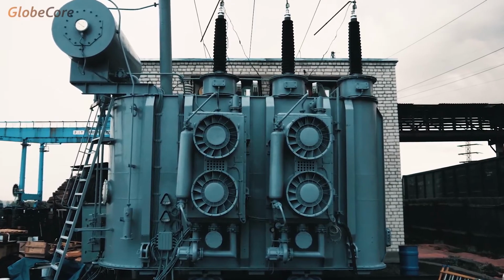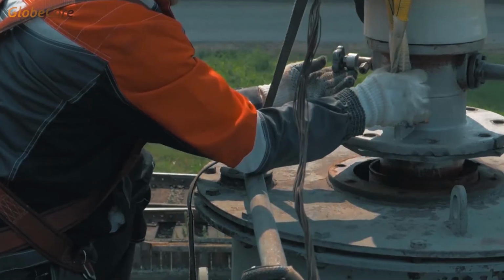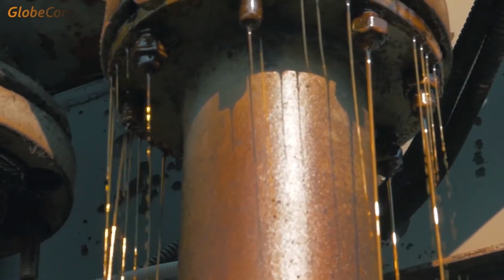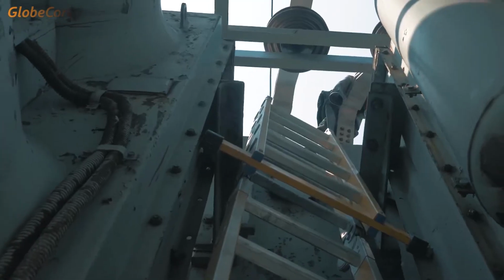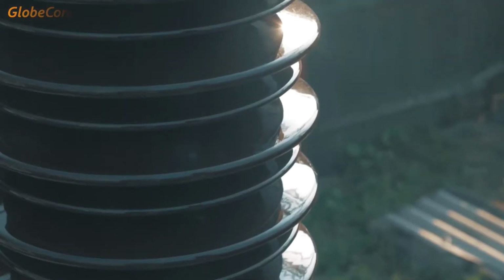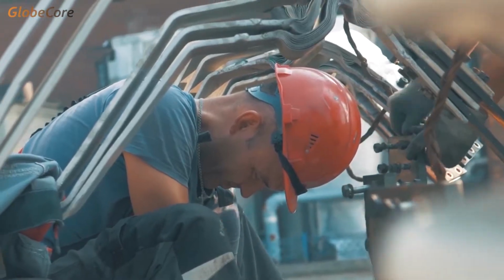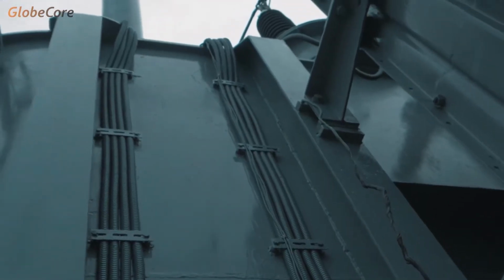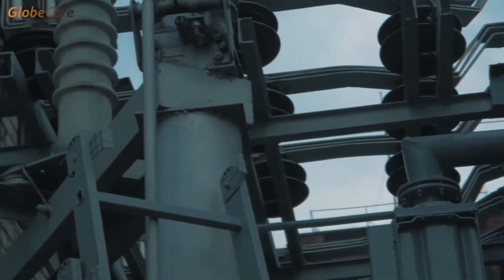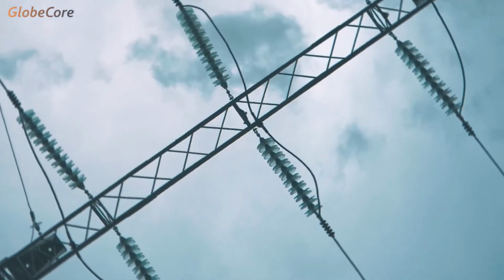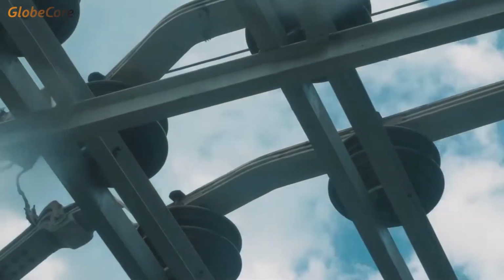Transformer windings may accumulate moisture due to their hygroscopic properties. Keeping a transformer open without preventive measures for any length of time is not recommended, so dry compressed air is necessary to prevent moisture from entering the transformer.